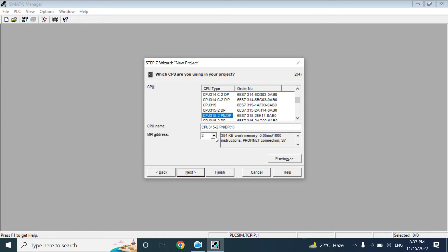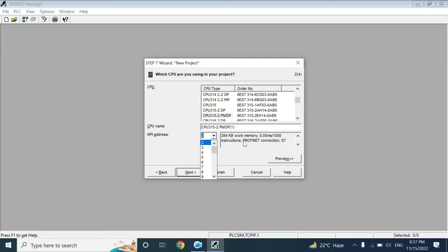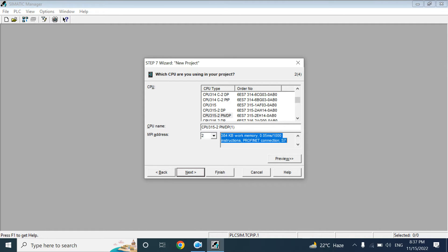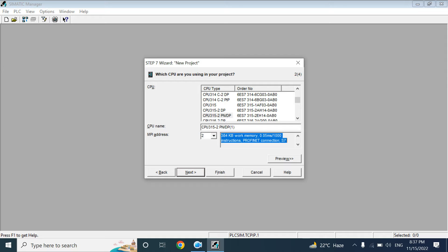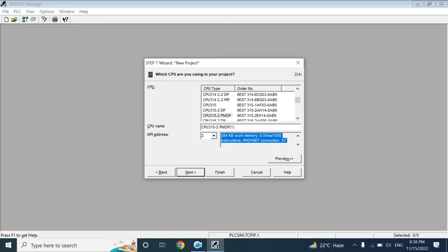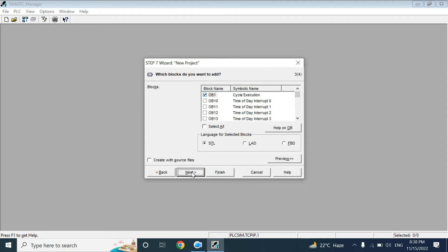Here you can see the MPI address, you can select up to 31. By default it is 2. When you select the CPU, here you can see the CPU work memory. But you know the Siemens PLC does not work without an extra memory card. That memory card is made by Siemens. There is a firmware software in that memory card, hidden. You cannot see that file. Now click Next.